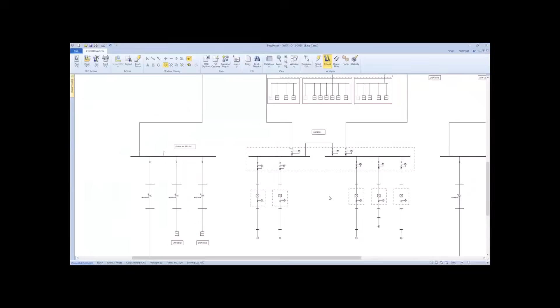The other thing that was really fascinating about this project was the use of the G&W relay, and yes, we're working on this. We have other medium voltage switchgears with this brand. I haven't worked with it before, but it seems like a very strong kind of switchgear, which can be used outside, underwater, in very tough situations. In this equipment here in medium voltage, as you see, the incoming and feeders don't have a relay.